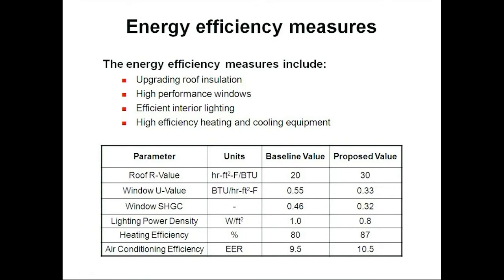The energy efficiency measures, which will establish our proposed building values, are upgrading roof insulation, establishing high-performance windows, efficient interior lighting, and high-efficiency heating and cooling equipment. In order to model those upgrades, we're going to change the roof R-value from 20 to 30. The window U-value will decrease from 0.55 to 0.33, and the window solar heat gain coefficient will likewise decrease to 0.32. The lighting power density will decrease by 20% to 0.8 watts per square foot, and we're using condensing boilers now — so instead of 80% efficiency we've jumped to 87%. Purchasing high-efficiency cooling equipment results in an EER of 10.5, up from 9.5. Here we see the new input values, which were acquired by adjusting the roof R-value, window U-value, etc., to the new values.